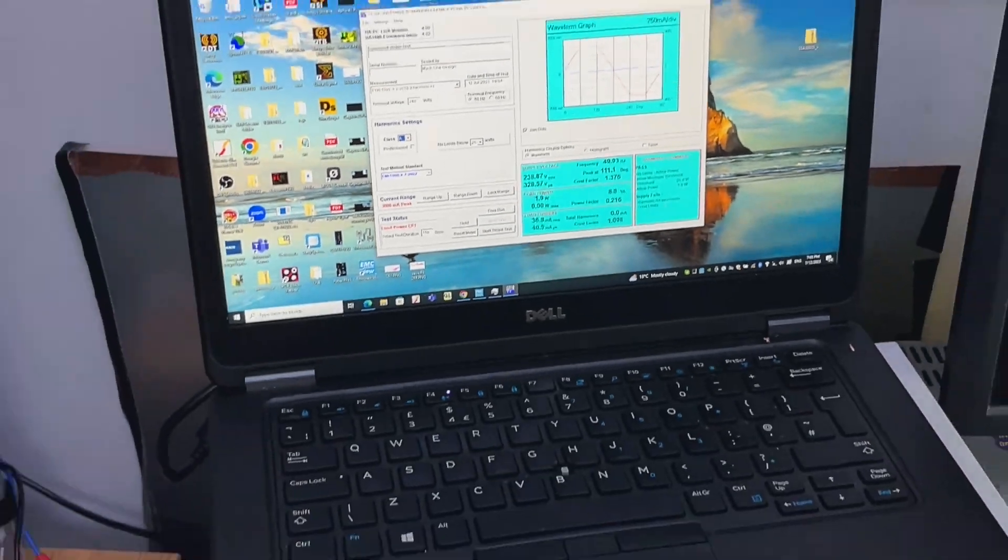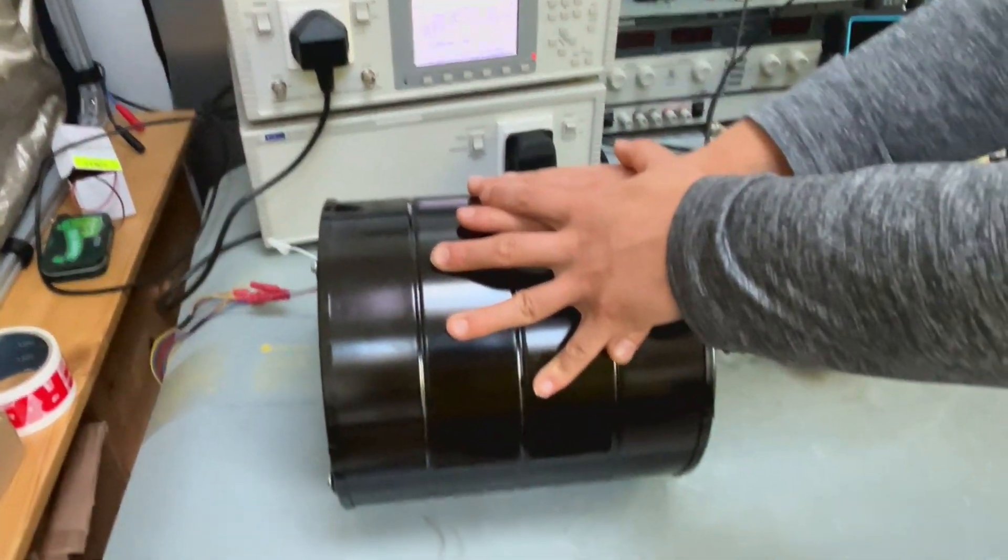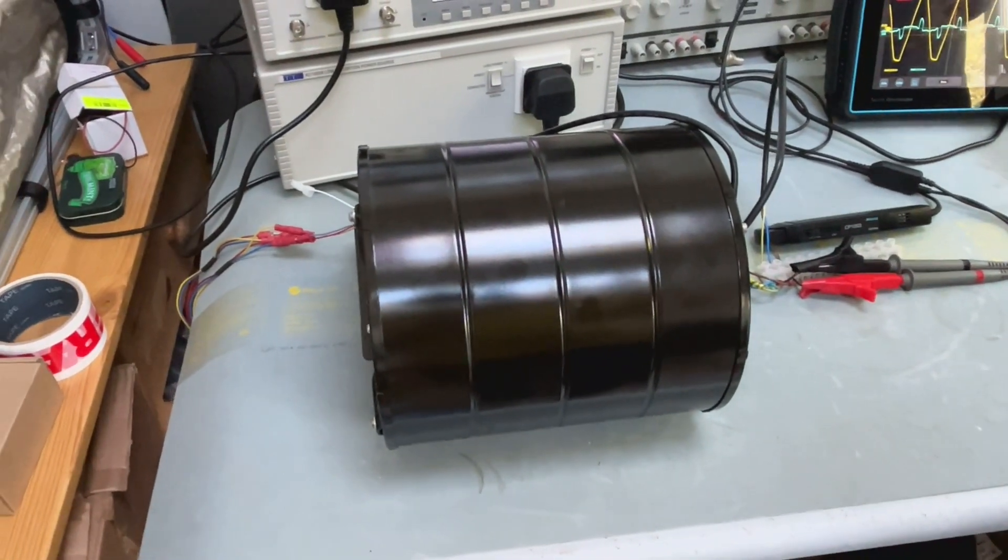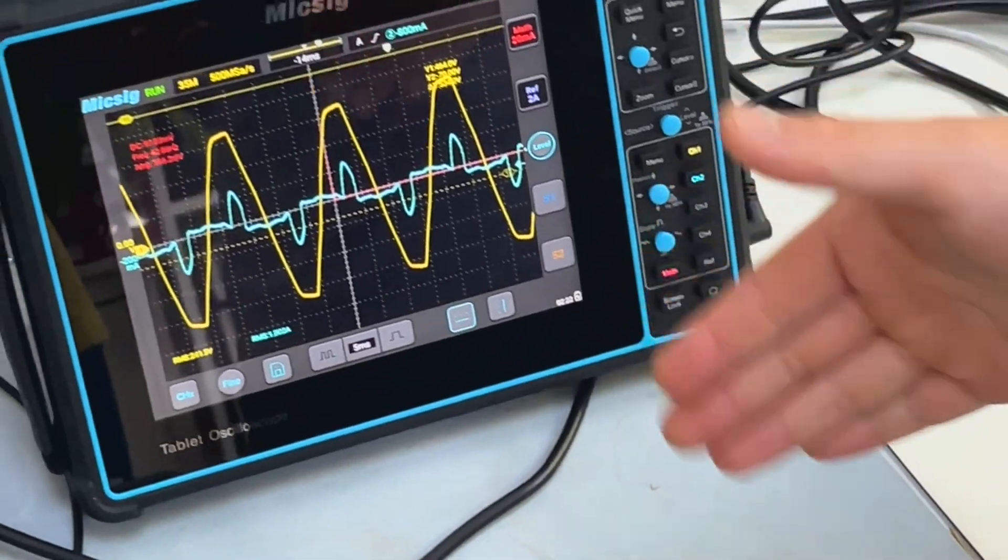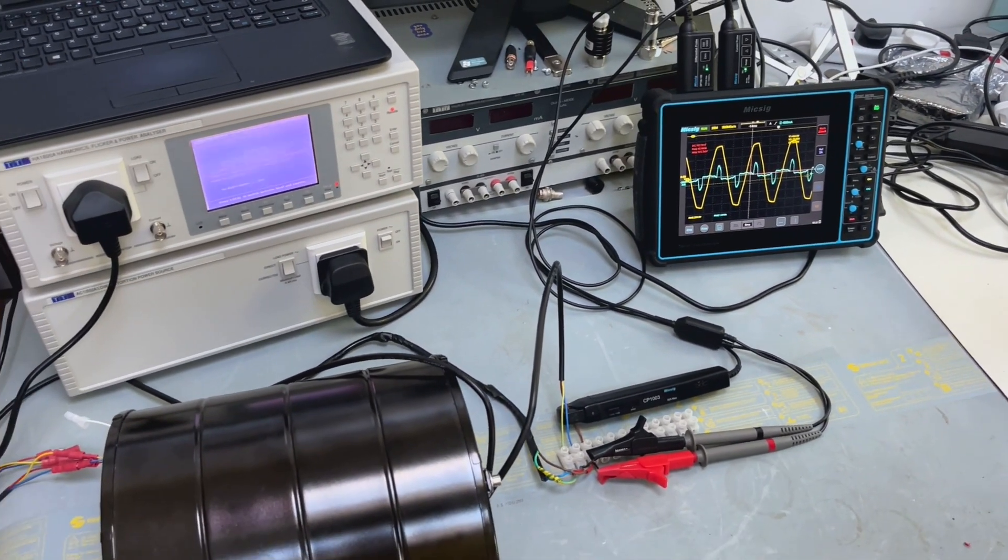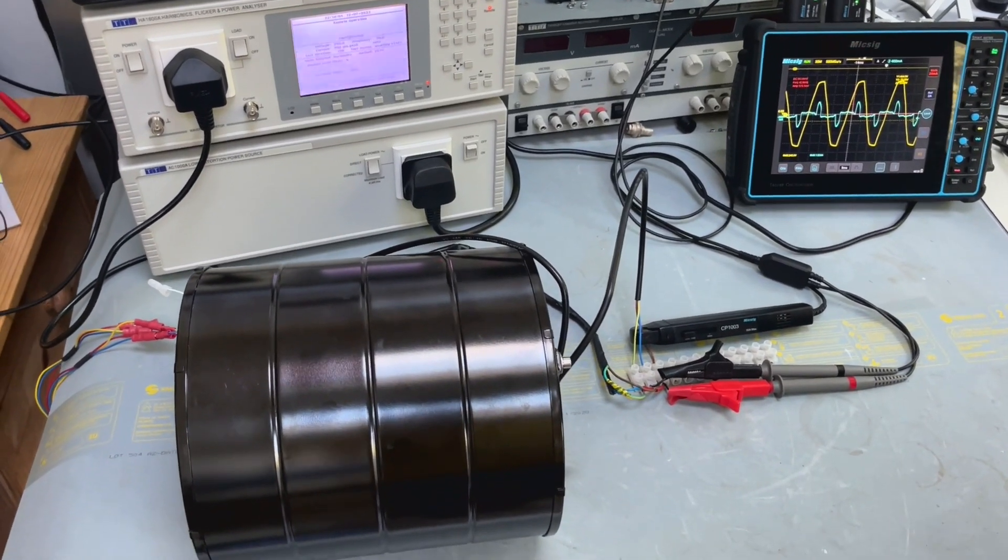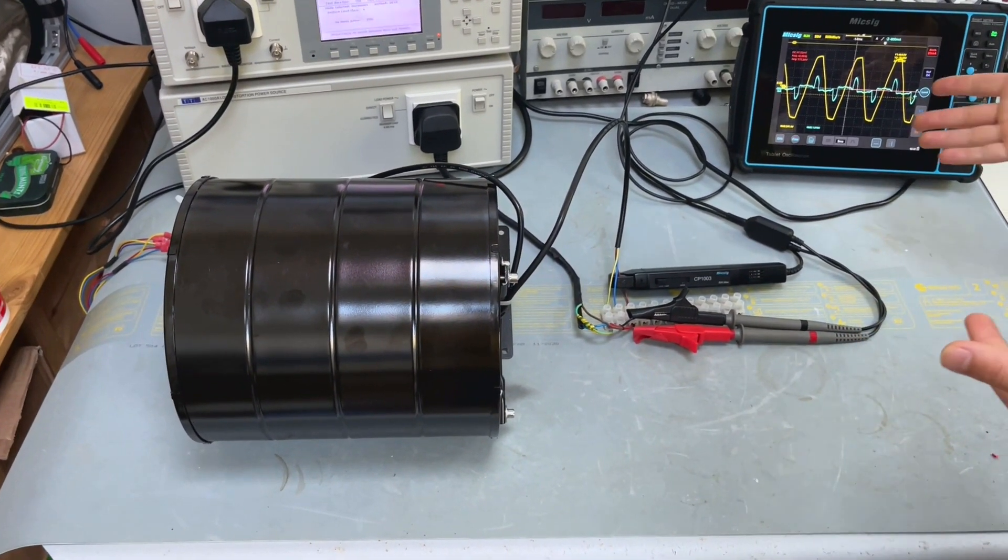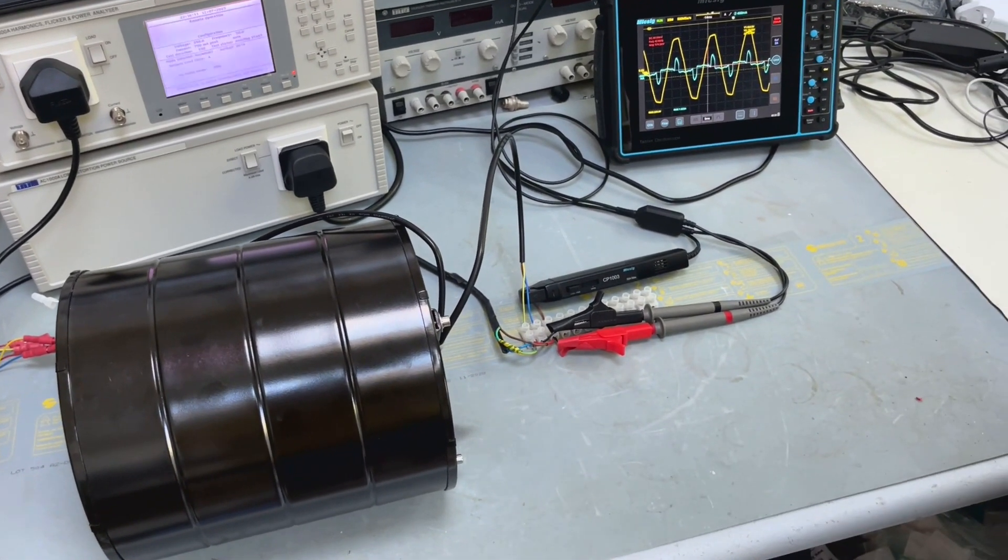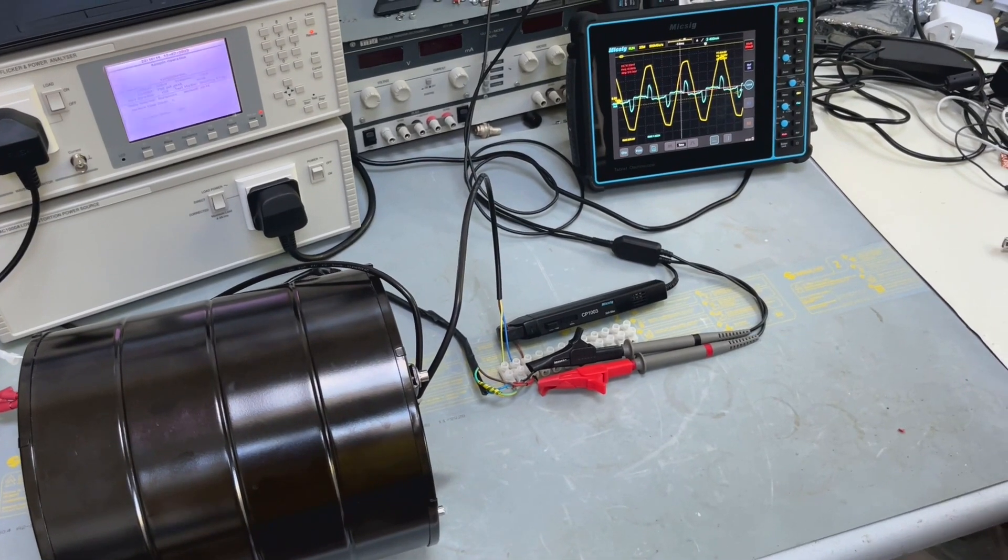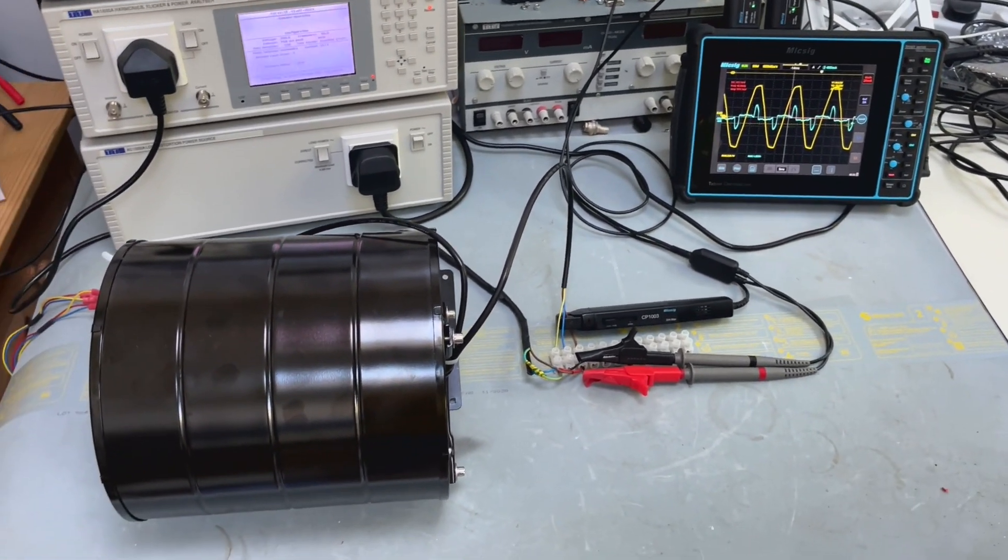So if I switch on the load which is this motor, the motor starts to spin and here you can see the voltage and current waveform we measured. The standard actually defines a very clean AC voltage waveform so that you can perform the harmonics test. In this case if the mains voltage is not clean so of course your current won't be clean, even if you are testing with a resistive load.